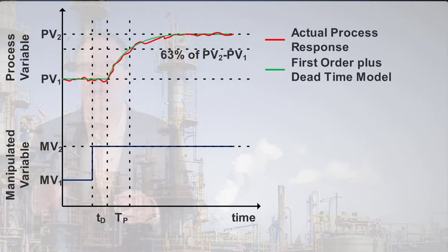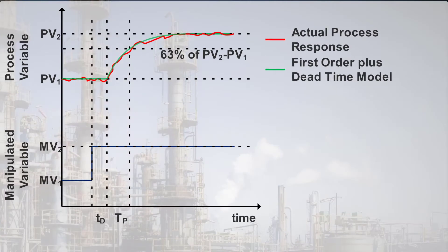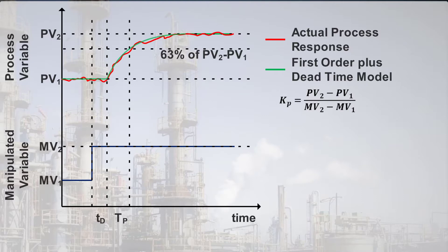Next, dynamics. We need to be able to speak about the magnitude of the response of a process variable to a manipulated variable, and the speed of that response. There are many different types of response possible, but in practice, we can approximate most of those responses with three parameters. First, the gain, K sub P, is the ratio of the steady-state change in the process variable to a change in the manipulated variable.